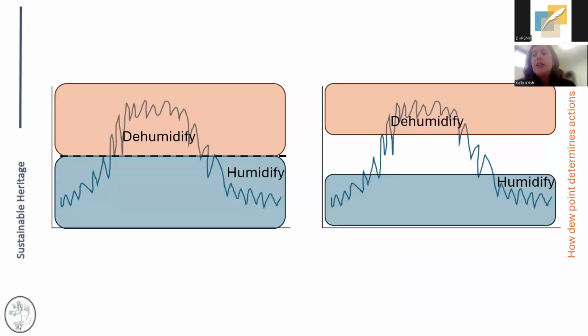Whereas on the right, you can see there are times of the year where the system's able to coast and I don't have to do as much work. Maybe that's about a third of the year or so. That could be pretty significant energy savings, and it may not come at any preservation risk at all, depending on the collection type. This is where, when we think about plus or minus 2%, plus or minus 5%, plus or minus 10%, that's what's expanding that gap and creating what we'd call a dead band, where the system can, as I said, not have to work quite as hard. So keep that in mind as well when we're talking about how dew point can be used to inform your set point. It can also help you understand when you're doing that work and how much you're asking your system to do.